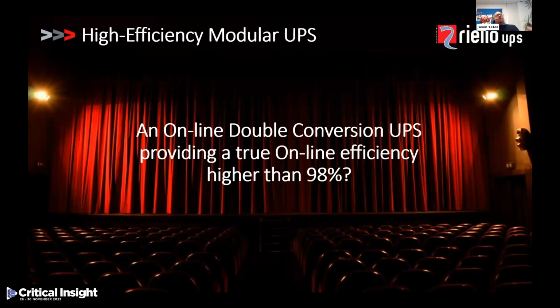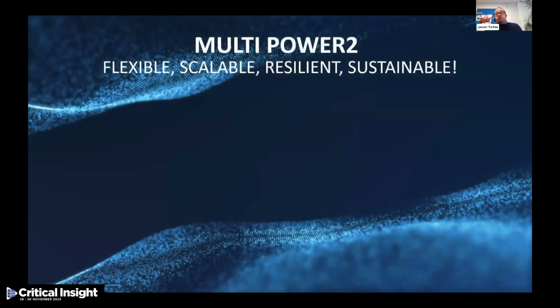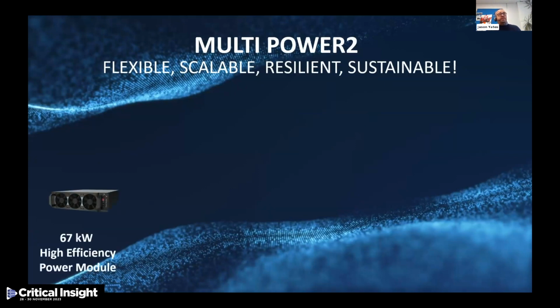What I want to do now is have a quick look at a typical high efficiency modular UPS. Unfortunately, this is a blatant sales plug on my behalf, I do apologize. This is an online double conversion UPS, produced by Riello, providing a true online efficiency higher than 98%. The system is the Multi Power 2. It's a flexible, scalable, resilient and sustainable UPS system. It's built around a high efficiency 67 kilowatt power module. This 67 kilowatt power module can be combined with 3 different power frames. We have a 500 kilowatt power frame.